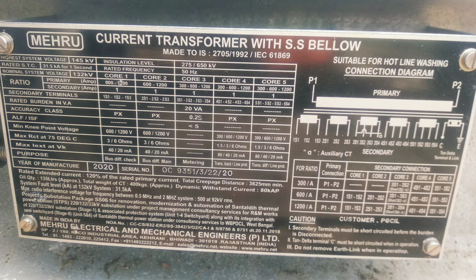In this video, we are going to see the testing procedures and also the test reports for a 132 kV CT, which means the CT ratio, which is having different types of taps in the secondary side, and also various cores are used in this CT. So we have taken one example as a 132 kV CT, and also for each tapping how the testing is carried out, and the test procedures and also the test reports, how it should be done, are mentioned in this video.